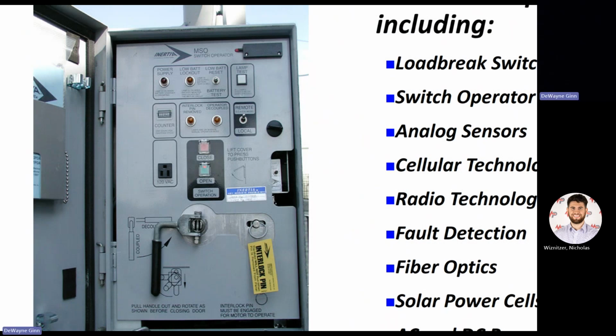So if you don't get halfway out, they would not then run out of power on your battery, and you wouldn't create an arc. So it will lock it out. It's got a low battery reset as well and a battery test. We run a battery test all the time on these to make sure. Interlock pin removal. If you look down to see that yellow tag, that's the interlock pin. We'll talk about that in a minute. The decoupler, the black handle to the left, that's pushed in. That's where we decouple the switch. So we'll talk about that.